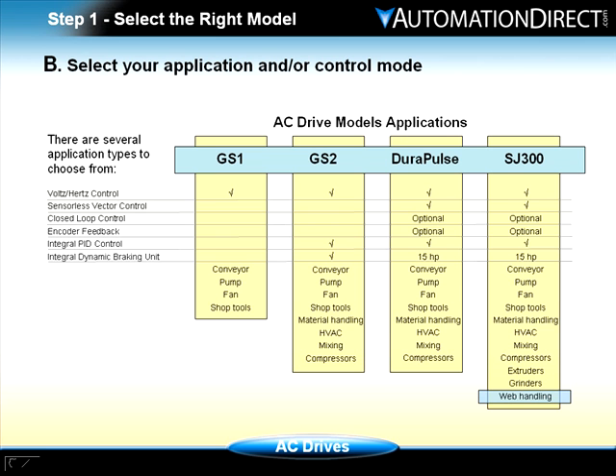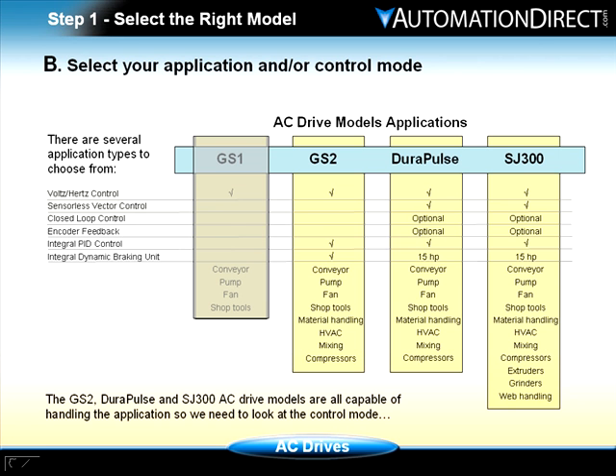Although the GS1 supports our application type, it does not meet our voltage requirements of 460 volts AC. Since the GS2, DuraPulse, and SJ300 AC drive models are all capable of handling our application, let's look at the control modes.